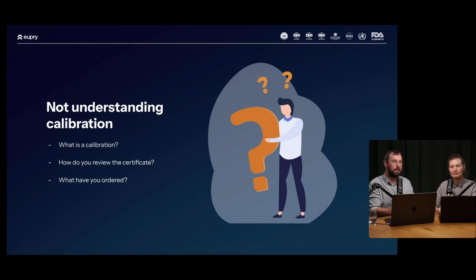We see an alarming amount of organizations just ordering a calibration, but you can't just order a calibration. You need to order specifically what it is you want, and is that actually what you've gotten? Because you'd also want to show consistency. Year by year, you should often not really change your calibration requirements. It can happen, it's totally fine, but it often leads to misunderstood reviews of calibration. So I think we've experienced a few times that we have customers purchasing a traceable calibration, and then when they have an auditor visiting, they come back to us and say, "Hey, why do we not have the little stamp in the corner?" Yes. So that's a very good example of understanding what a calibration is and what you actually purchased. Absolutely.